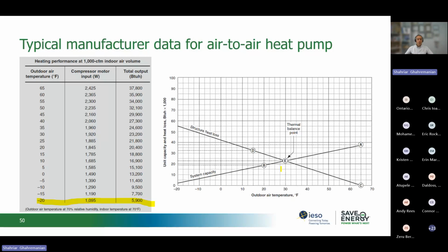This also depends on our building envelope. Is our building up to today's code, or is it, let's say, 40 or 60 years old, where the envelope doesn't hold the heat and it is emitting heat out to the outdoors? So this is the balance point again: when the contractor designs or sizes the heat pump for your facility, they have to show you how much extra heat is needed at different outdoor temperatures. Then, based on the location, the city, they have to choose the right one. For example, in Toronto, let's say the coldest recorded temperature, averaged over 30 years, is between minus 18 and minus 22 degrees Celsius.